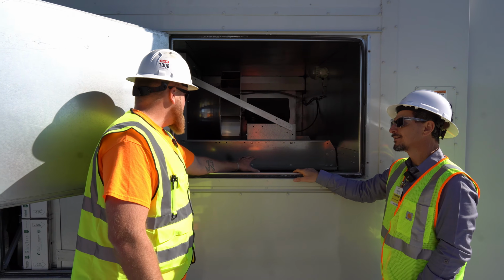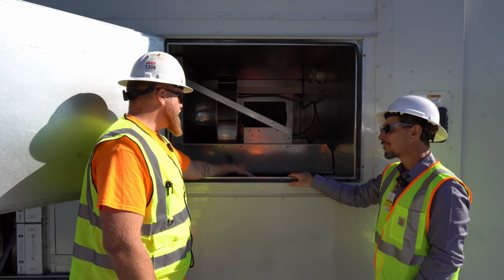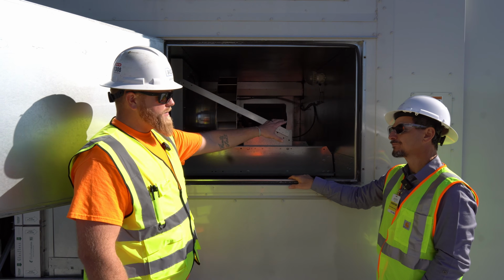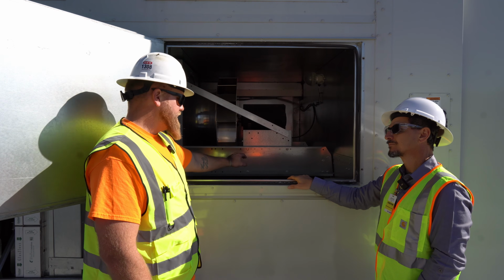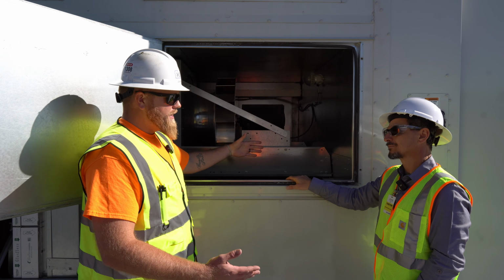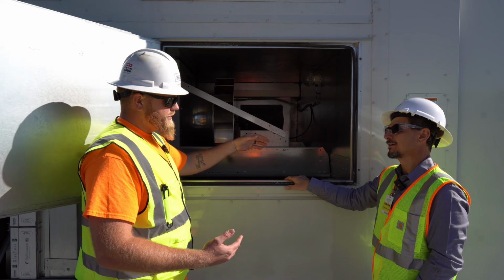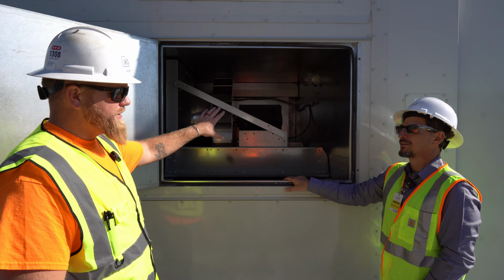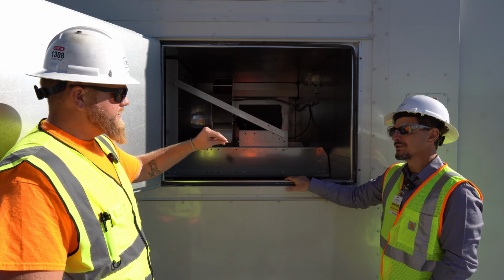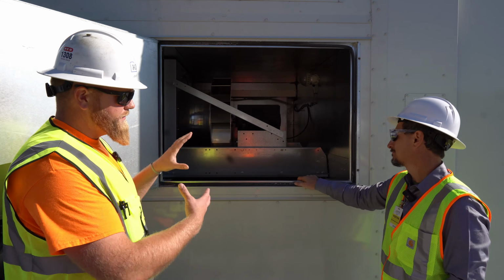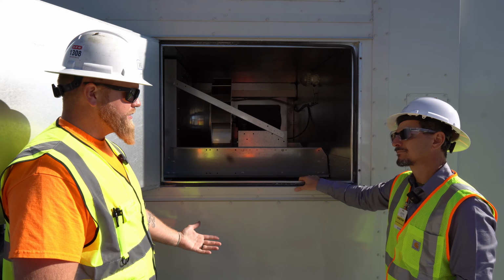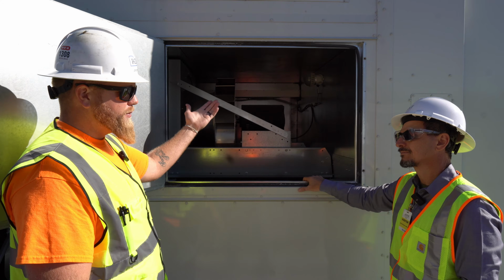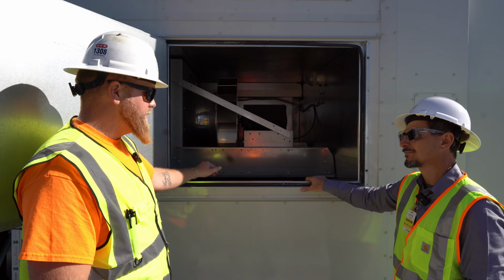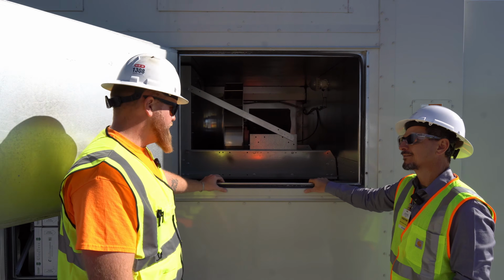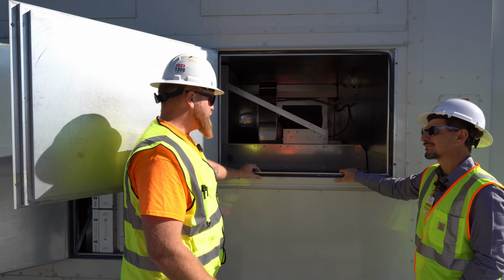We take the pressure of the fan cavity, and then there is a high static pressure switch. So if anything happens downstream of the system, a damper collapses or a damper closes, something along those lines, it'll sense the high static in the system. So it doesn't blow the duct out? Yep. Or blow the system up here. If anything below the system turns off or closes and the pressure up here exceeds 2 inches or 4 inches, whatever the design was, that high static will trip and turn the fans off.